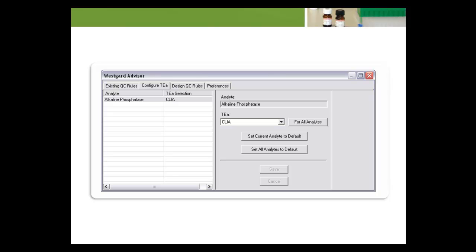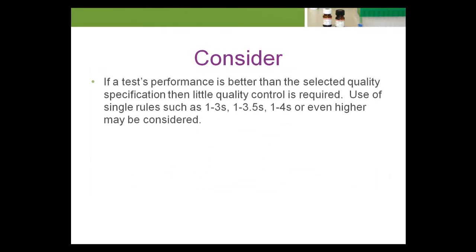This use of TEA evaluates whether opportunities exist to adjust the QC rules. A few key points to consider are if a test's performance is better than the selected quality specification, then little quality control is required.